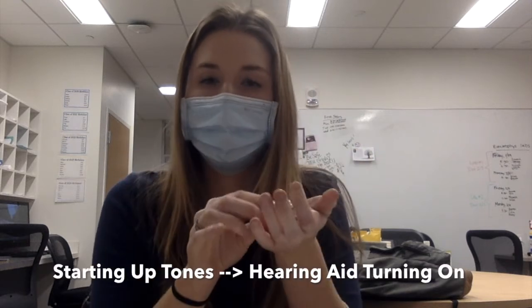Let's say you do that and you don't think you hear anything, you don't hear any feedback. You can do, like we mentioned before, opening and closing of the battery door. Again, this will turn the hearing aid off and then back on. And when you turn it back on, you should be able to hear a few starting up tones. That will mean that the hearing aid is working correctly and that the hearing aid is on. So once you've done your listening check, if you find that the hearing aid's not turning on or isn't working, then you can tell your client or their parent that you think there's something wrong with the hearing aid and they need to go see their audiologist.